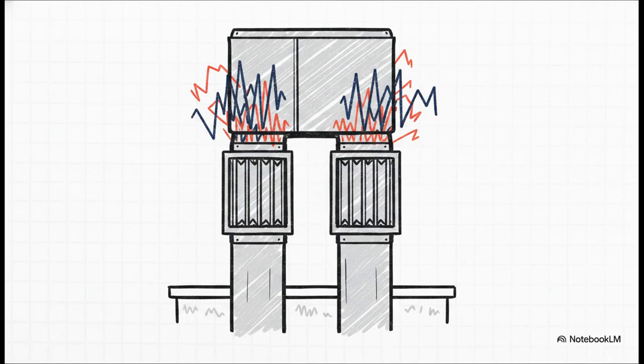When you're dealing with massive rooftop package units, the noise doesn't just seep through walls. It plunges straight down into the floors below, right through the metal ductwork. The go-to, relatively low-cost method for choking off that sound is the duct silencer. These things are incredibly versatile. You can get them in round or rectangular sizes, and they are completely scalable, meaning you can build them to handle massive systems just by stacking more modules together.